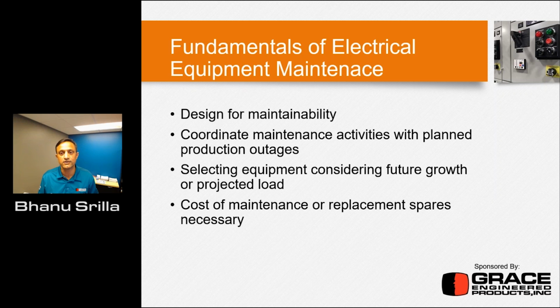So you probably plan for a 5000 or 4500, depending on whether you foresee an increase to that load, so that you don't change the main breakers on a short-term basis. And the cost of maintenance, replacement, and spares necessary for these fundamental maintenance practices also has to be taken into consideration, because you need to understand the impact of various types of equipment, and you want to standardize those to make sure that you have the same type of breaker, and you have 2 additional in your spares. So if something goes wrong, you have this extra spare that you can just rack in and bring the production back to normal, right? And you also need to make sure that your replacement spares, like your fuses or any other regular consumables, are kept in place as well, okay?